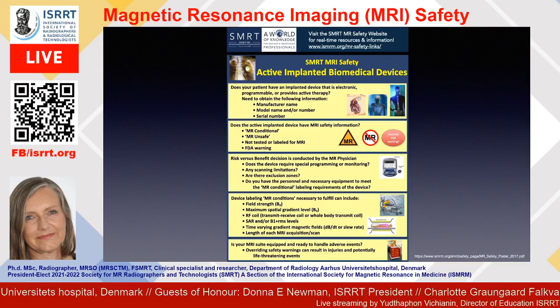Labeling of MR conditional implants. Here it is such that all medical implants have to be tested by their manufacturers for MR safety and labeled according to the standardized terminology. And that's the ASTM F2503-13, Standardized Practice for Marking Medical Devices and Other Items for Safety in the Magnetic Resonance Environment, the ASTM.